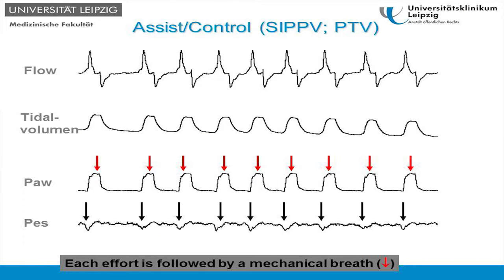And here you see a longer recording of this. Here's the inspiratory flow, the tidal volume. The frequency is not quite the same. It's changing a bit depending on the patient's effort. This is esophageal pressure, and we see that the patient is getting a machine breath every time the esophageal pressure decreases, so the machine has been able to pick up every breathing effort of the patient and help the patient with the inspiration.